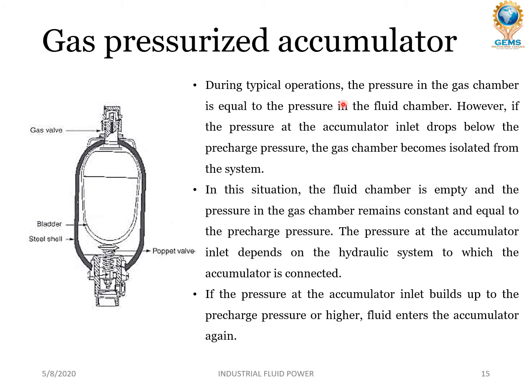A decrease in fluid pressure causes the gas to decompress and discharge the stored fluid into the system. During typical operation, the pressure in the gas chamber is equal to the pressure in the fluid chamber. However, if the pressure at the accumulator inlet drops below the pre-charged pressure, the gas chamber becomes isolated from the system. In this situation the fluid chamber is empty and the pressure in the gas chamber remains constant and equal to the pre-charged pressure. When the inlet pressure builds back up to the pre-charged pressure or higher, fluid enters the accumulator again.